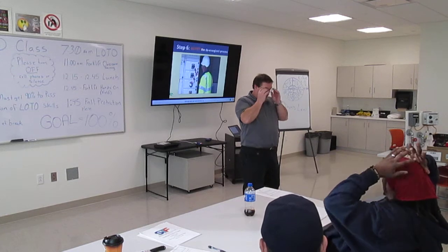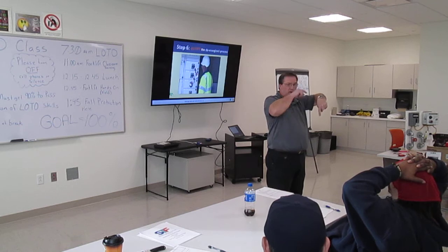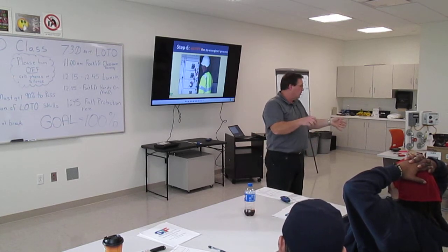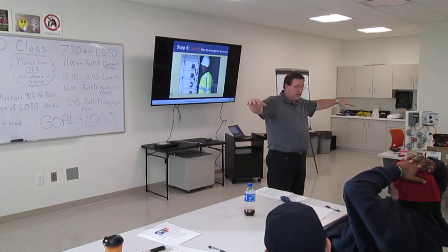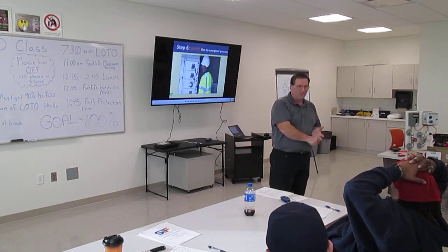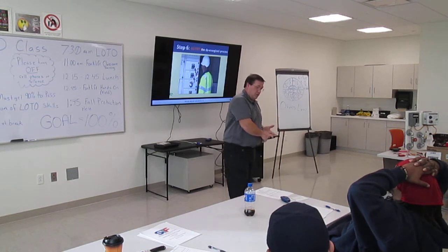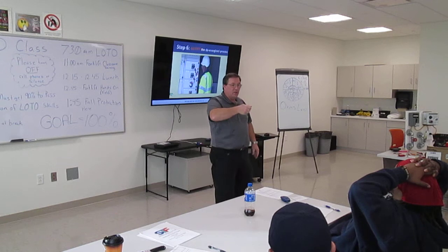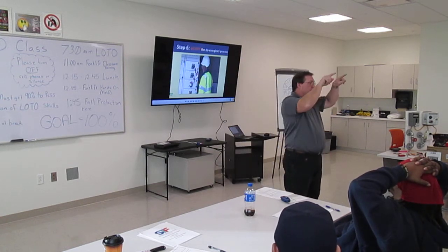So what we're doing is taking those plugs off. The power source came from over there, to this plug and that plug and that plug, so like three different plugs, because the disconnects were in the plugs. But when that burned up, you had to shut all three disconnects off. That shut the entire line down, which caused a humongous problem. So we were out there putting new disconnects on for every plug, so we could work on one at a time. So we went upstairs to the panel room, and we looked at the schedule on the wall.